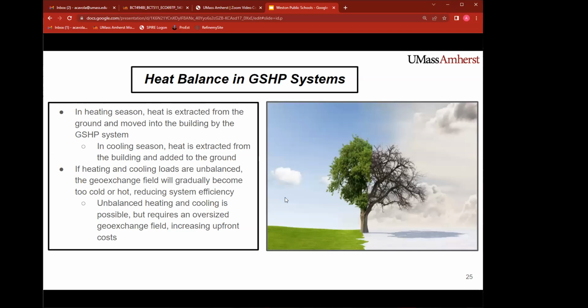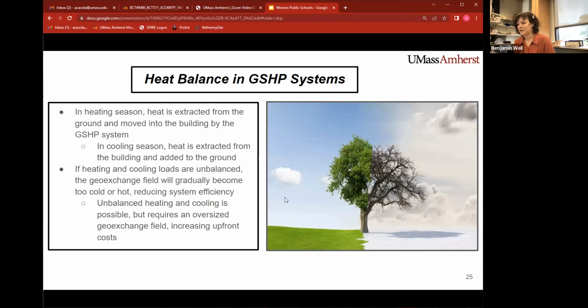So part of our exploration of the feasibility of a district ground source heat pump system involved modeling the heat balance of the system. So remember earlier in the presentation when I said the ground source heat pump system essentially uses Earth as a long-term thermal storage or solar thermal battery? In heating season, heat is extracted from the ground and moved into the building by the ground source heat pump system. And in cooling season, heat is extracted from the building and added to the ground. And if heating and cooling loads are unbalanced, the geoexchange field will gradually become too cold or too hot, and this will reduce the system efficiency. And unbalanced heating and cooling is possible, but it requires an oversized geoexchange field, and this will increase upfront costs.